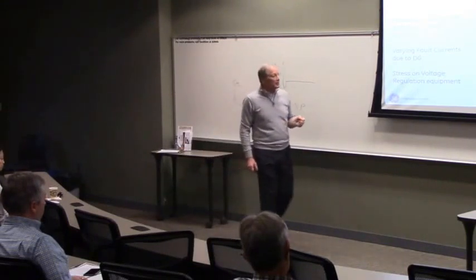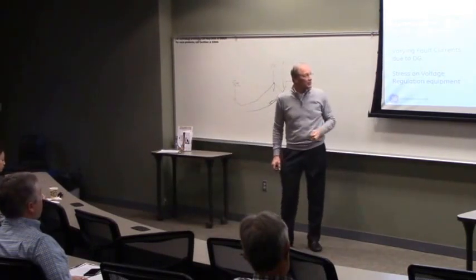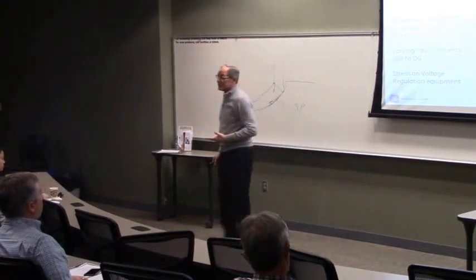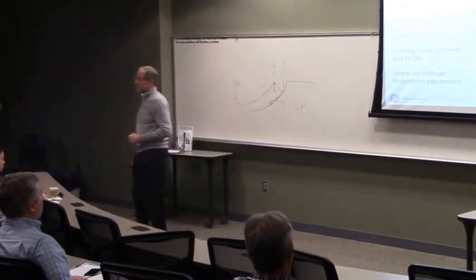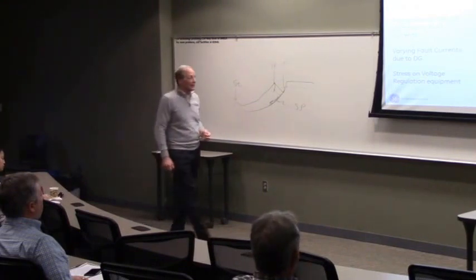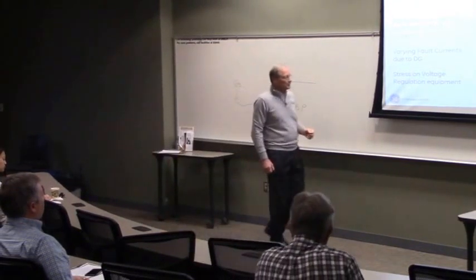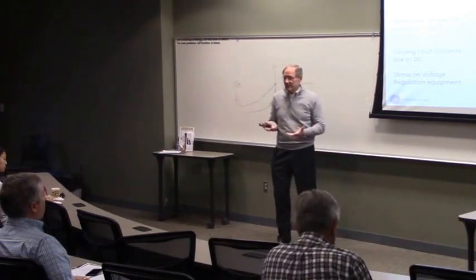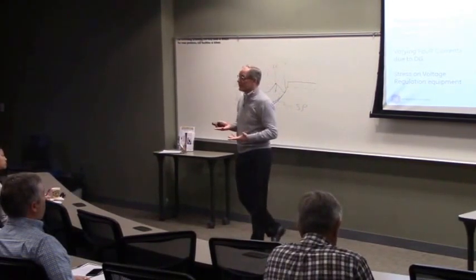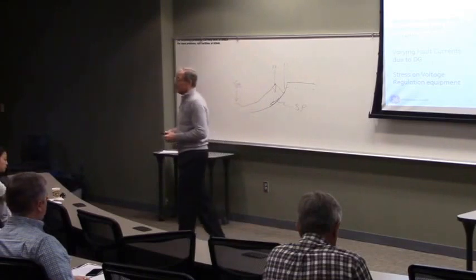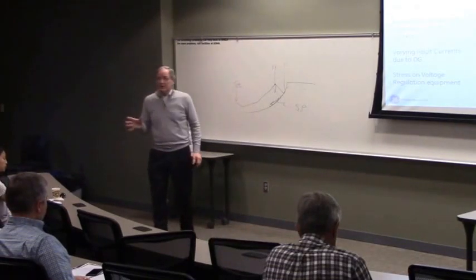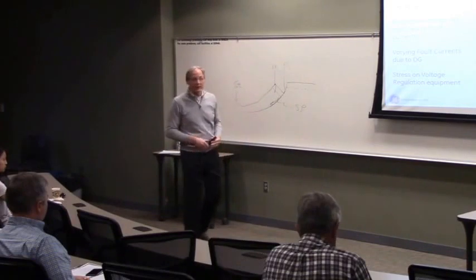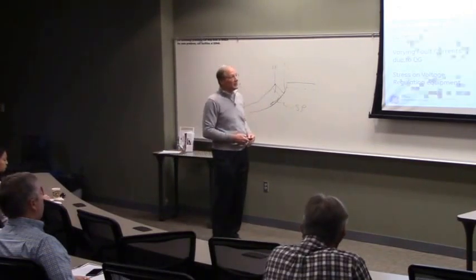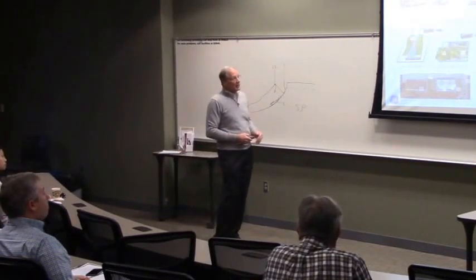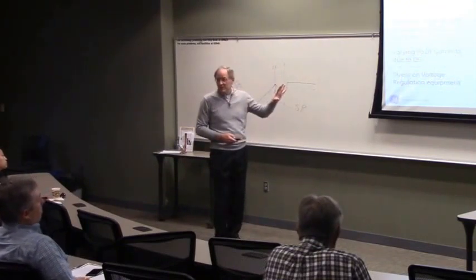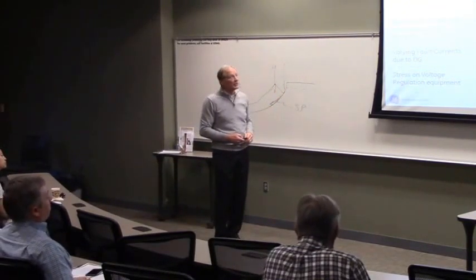And the other thing is the fault currents from the load side contribution due to the DG are varying because of the intermittency of the DG. They're not constant. And because of the volatility of the intermittency that is created on a distribution feeder, there's a lot of stress on the voltage regulation equipment. Okay? So you have to think about that. What are the operational impacts of distributed generation?